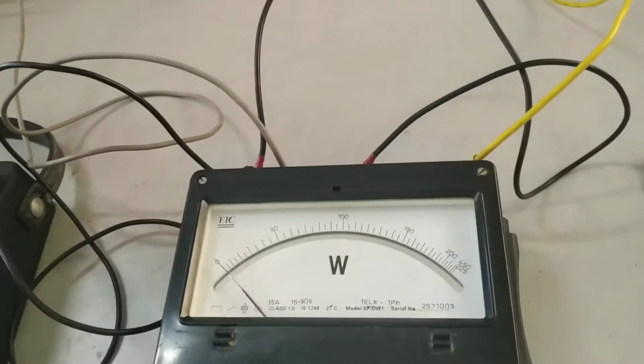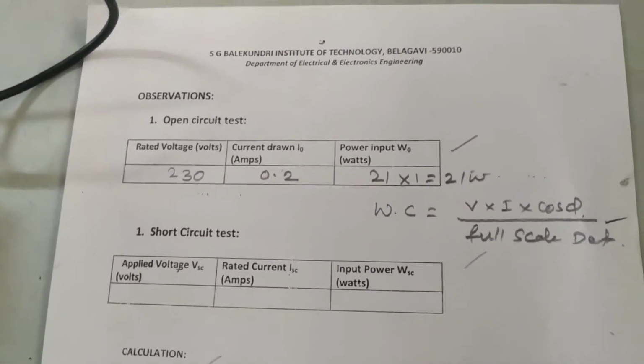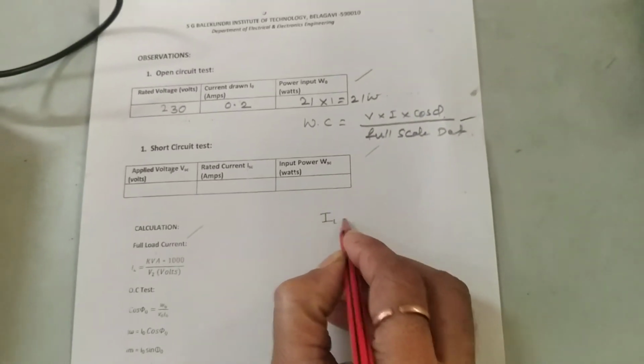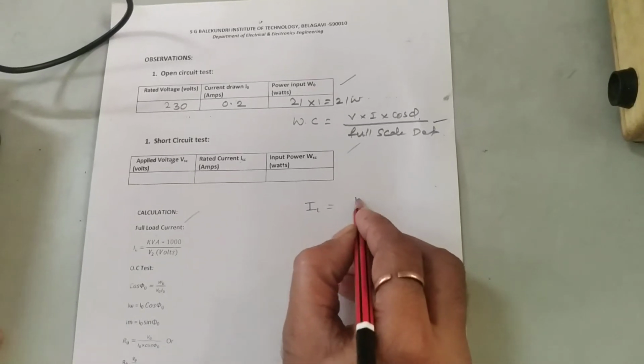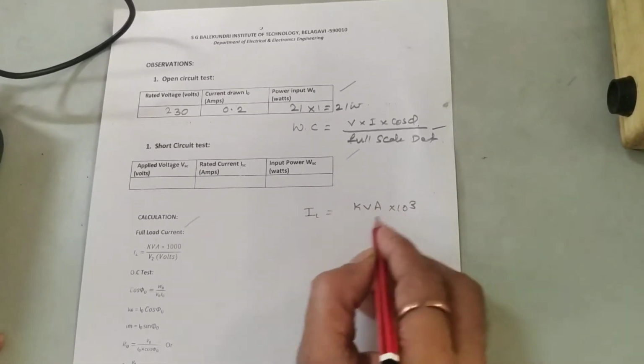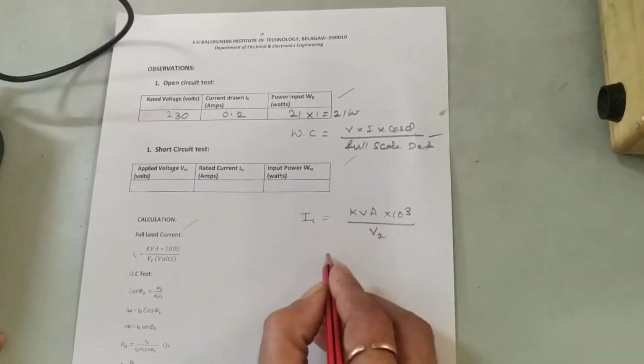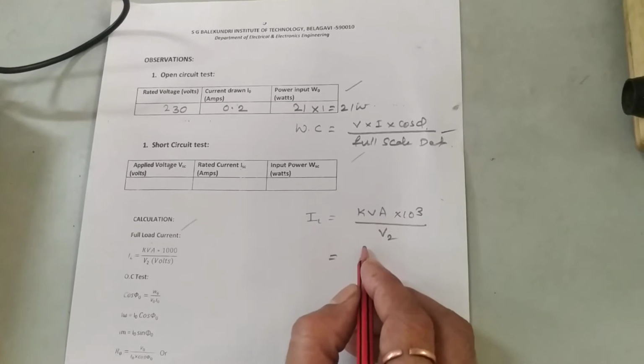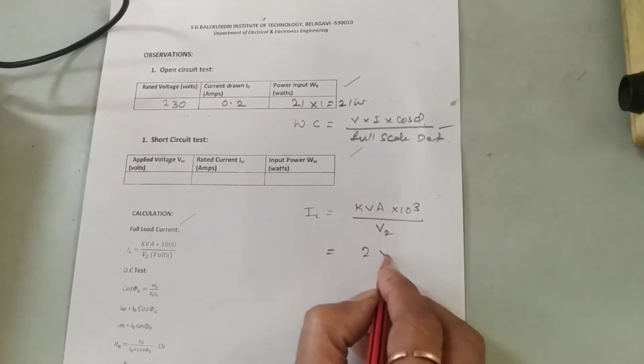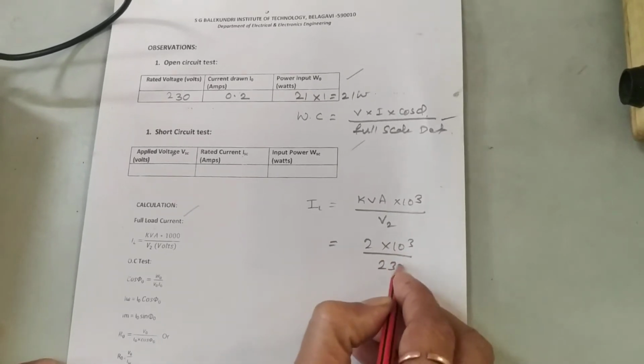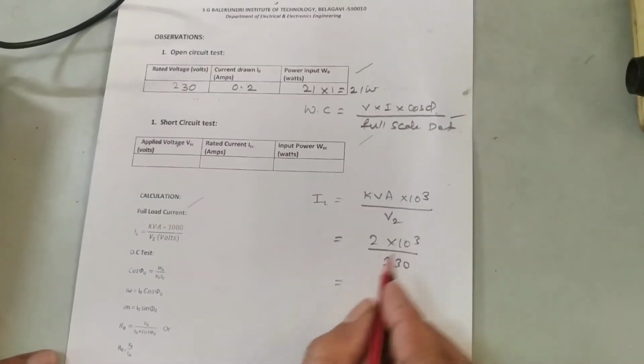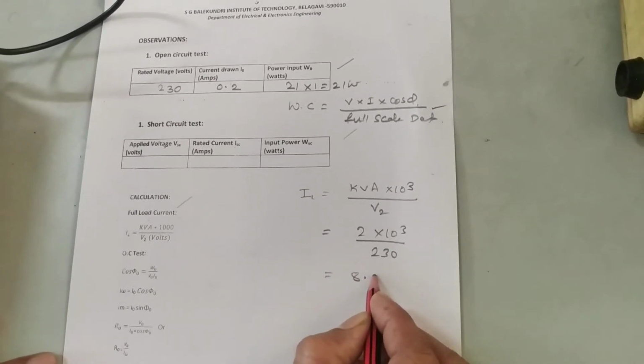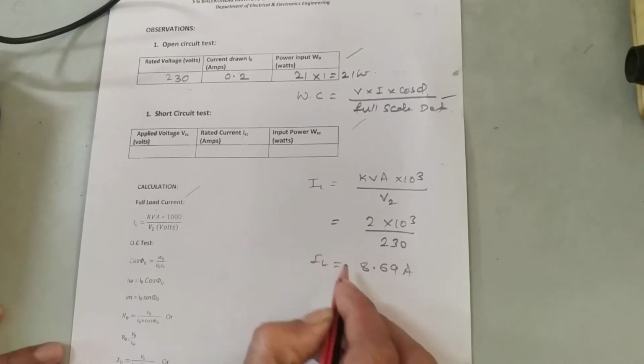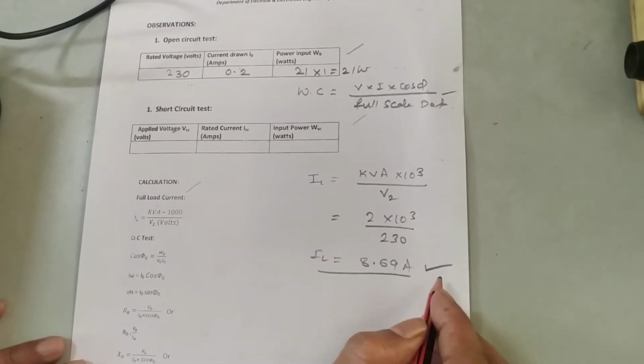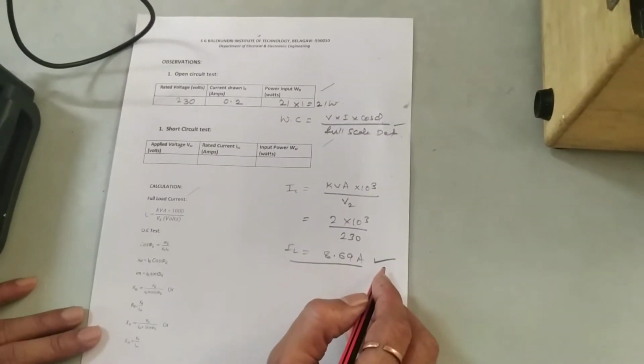To conduct this test, we need the rated current of the transformer. It can be calculated as kVA into 10 raised to 3 divided by V2, the secondary side voltage. The kVA rating of the transformer is 2, so 2 into 10 raised to 3 divided by 230. By calculating this, we get 8.69 ampere, which is nothing but the rated full load current of the single phase transformer on which we are going to conduct the short circuit test.